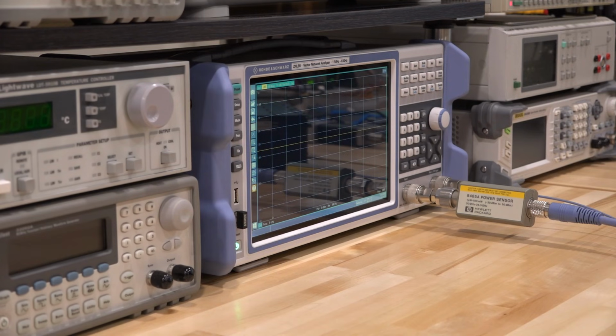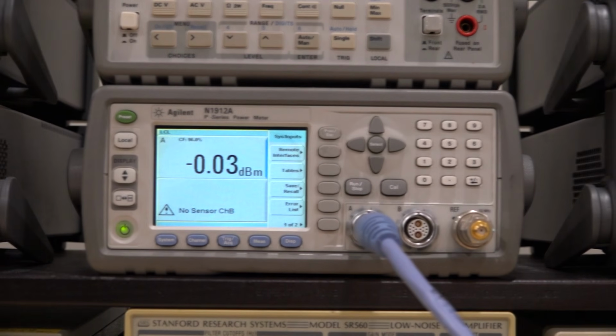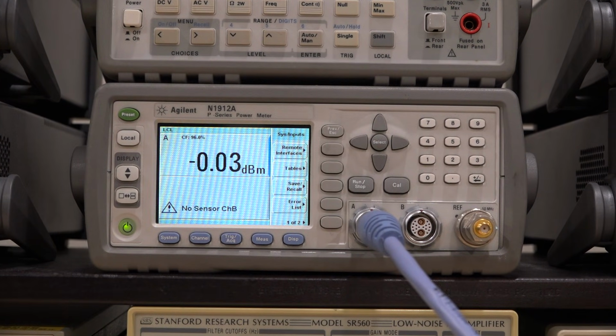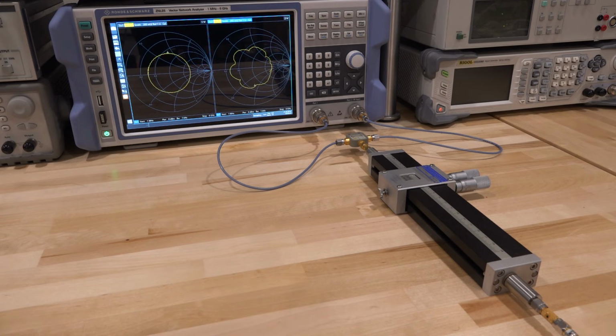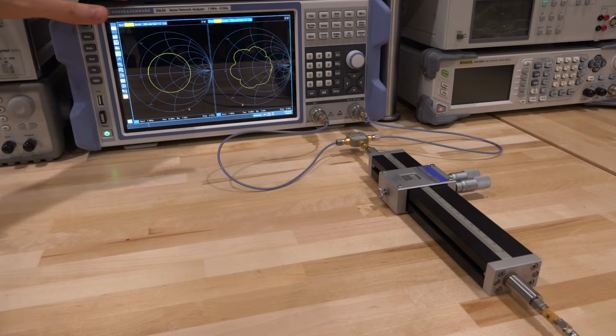And for completeness, here I have the output of the network analyzer connected to a power sensor, and the power sensor is connected to my power meter, set to 6 gigahertz and 0 dBm. And check it out. As I said, it really puts out 0 dBm across the entire band within less than 0.3 dB. So it's very good. Harmonics are good, phase noise is good, output power is accurate. Really couldn't ask for anything more. And I would also like to take a quick look at the mixed mode S-parameter measurement capability of the instrument. As I said, you can do a common mode calibration.